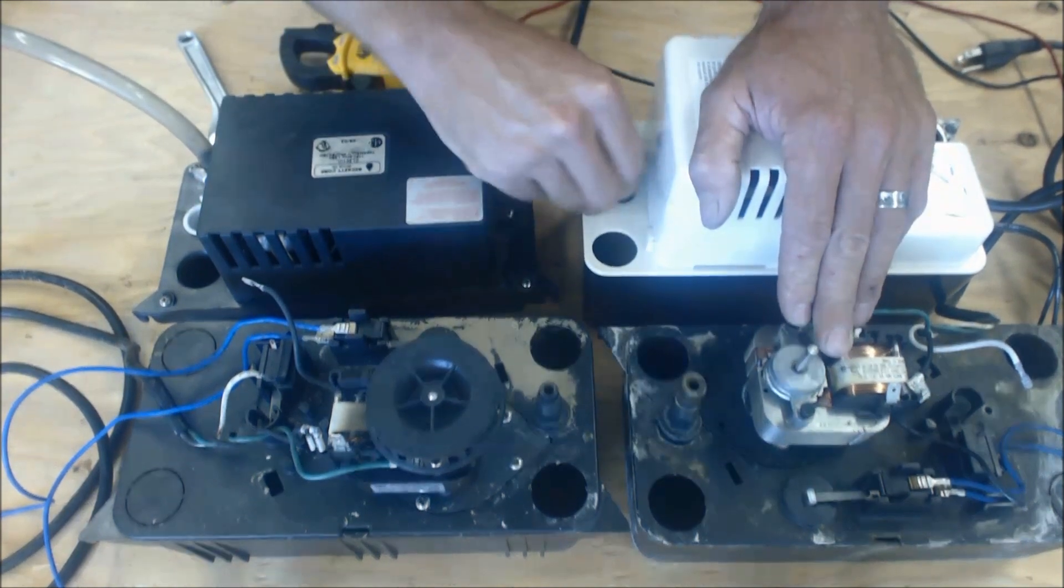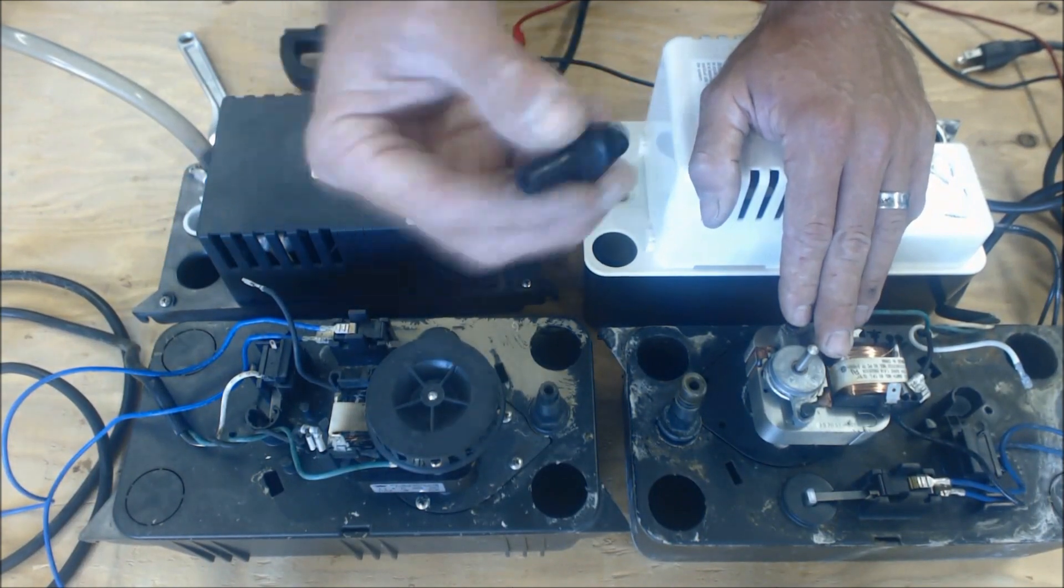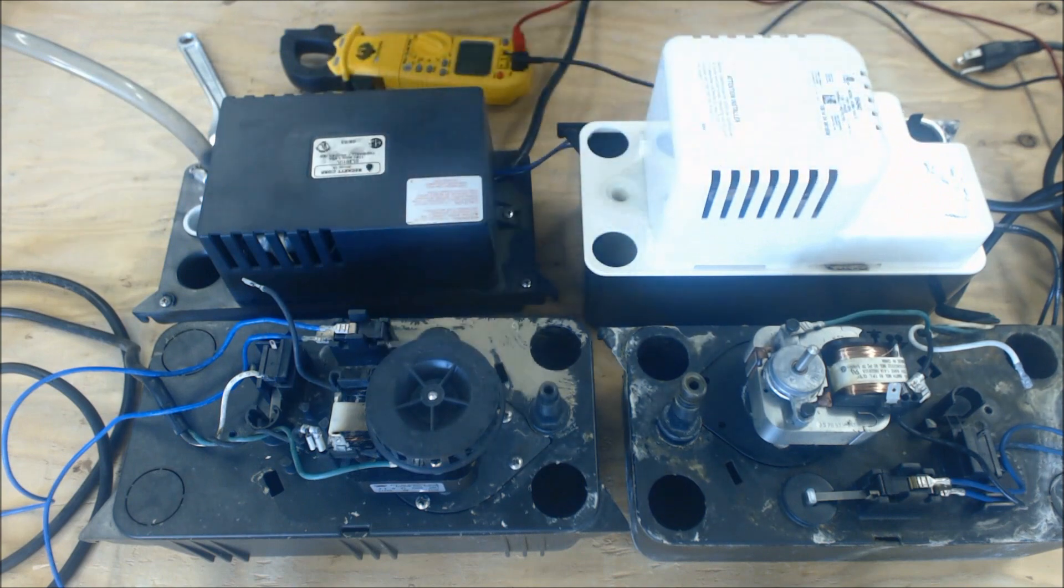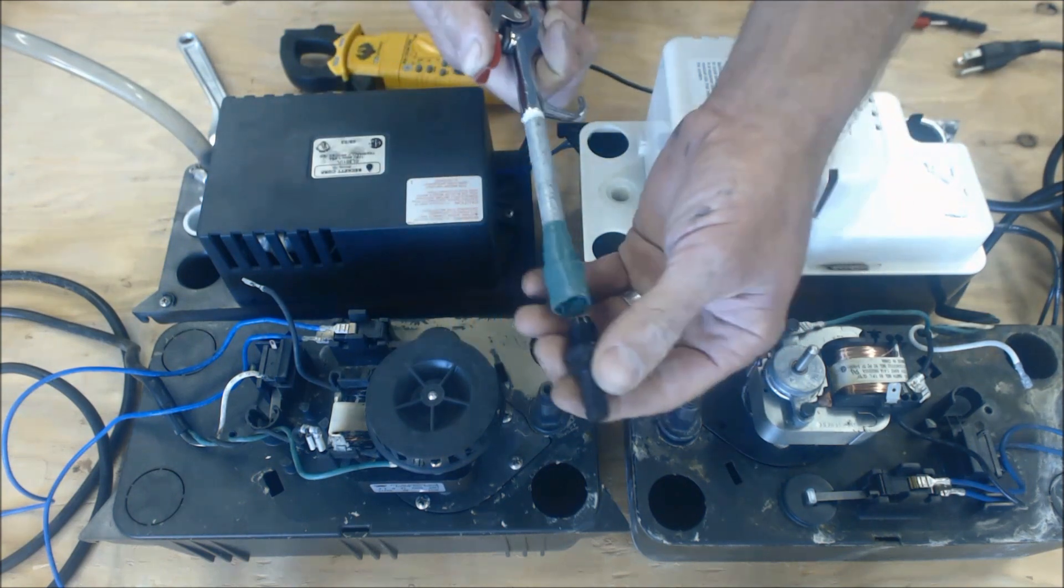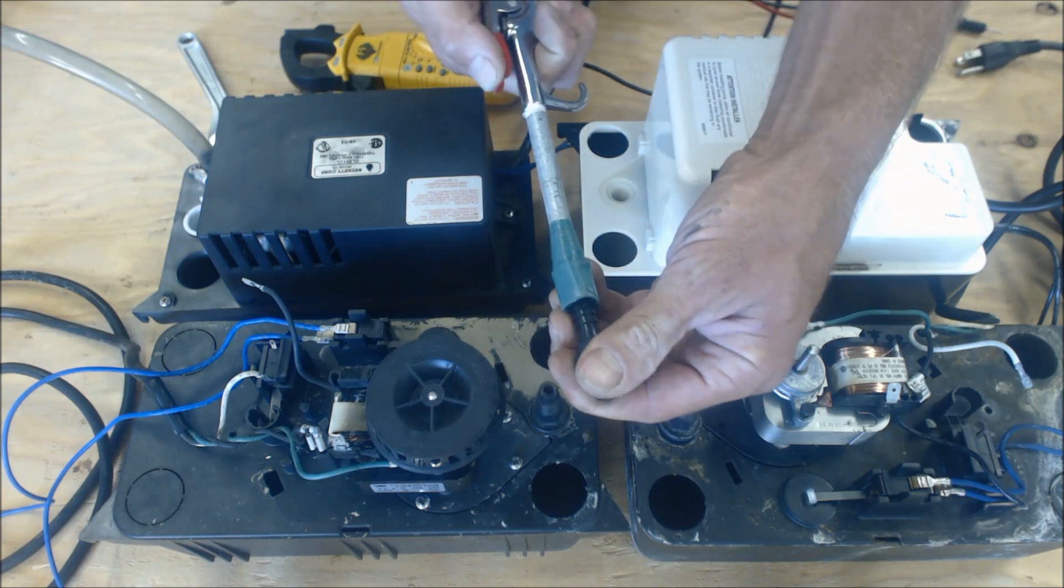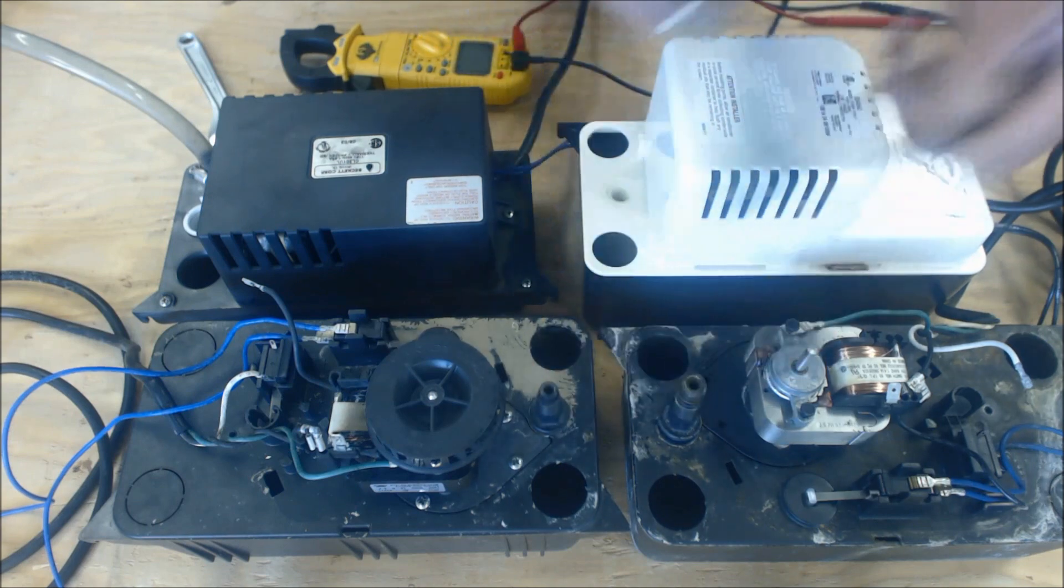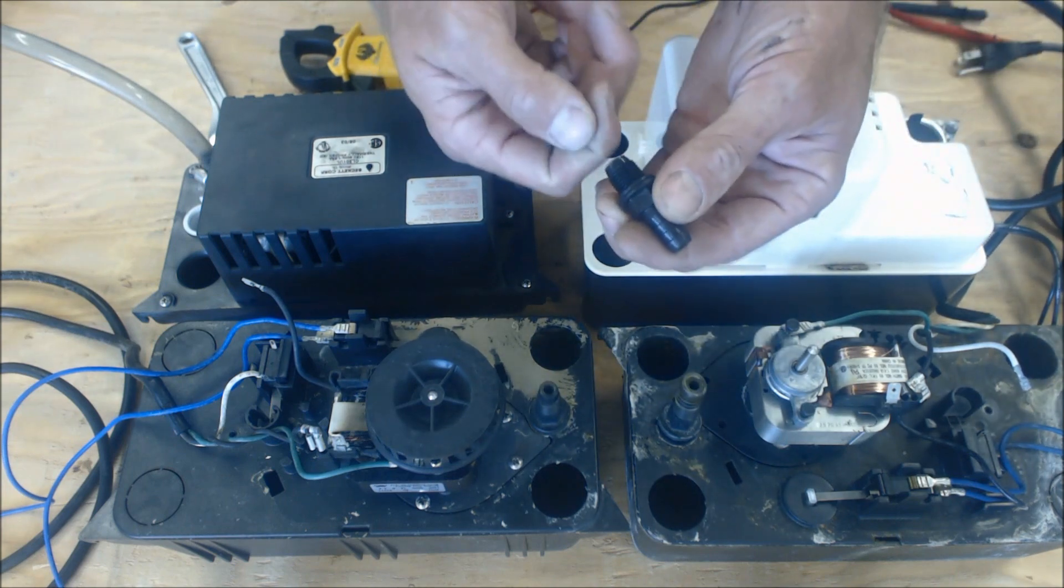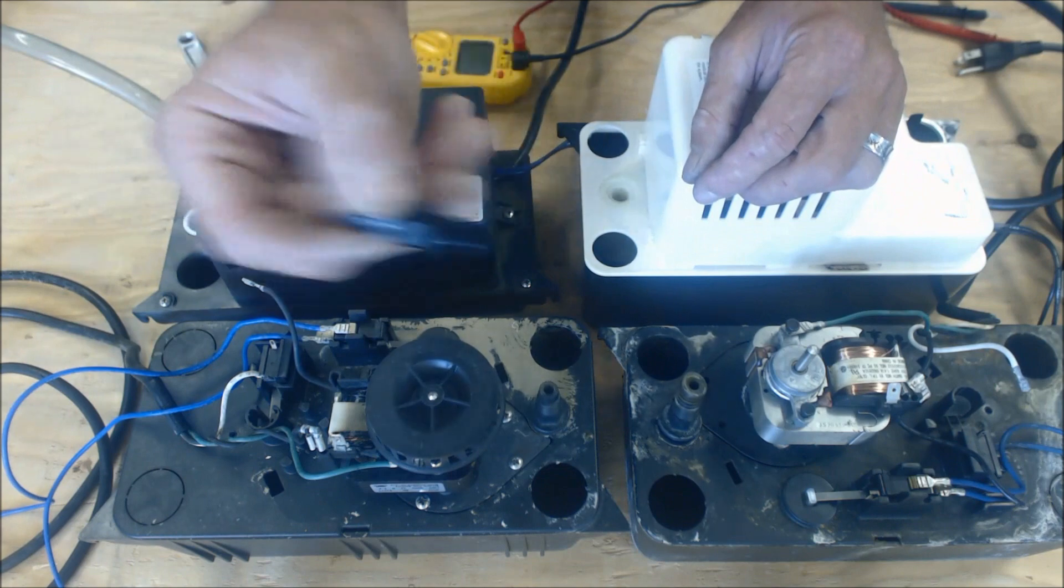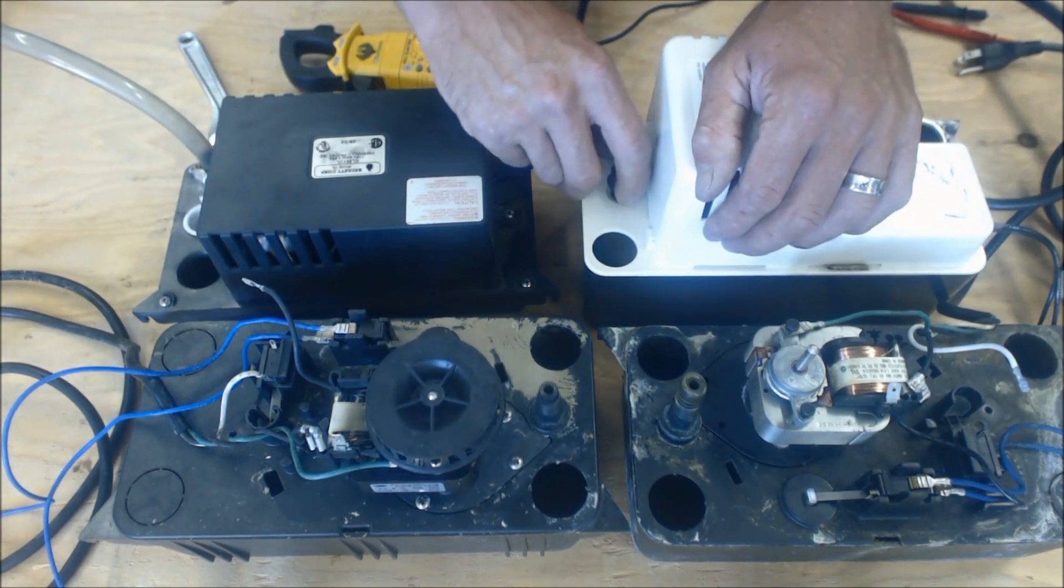The Beckett ones have a little ball float in there, so you can feel the ball jumping around in there. And what you do with them is you just take your compressed air and you blow it back and forth. The compressed air doesn't have to be crazy hot. You can put some water in there and then blow it, water in there and blow it, but that will clean that out so you can hear the ball moving back and forth in there correctly.